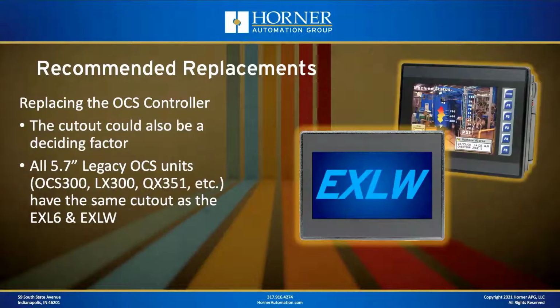Now, another factor you might want to consider is the cutout. For a really long time, back to the early 2000s, we've been selling 5.7-inch OCS models. That's because, especially back in those days, 5.7 was the most popular size for user interfaces, whether they had built-in PLCs like an OCS or whether they were just separate user interfaces. So we've offered them for many years. The newer products, the EXL6 and the EXLW, both have the exact same cutout that you'll find on any 5.7-inch Horner unit we've ever sold. So they often will be a really good choice, especially if you're replacing a 5.7-inch unit.